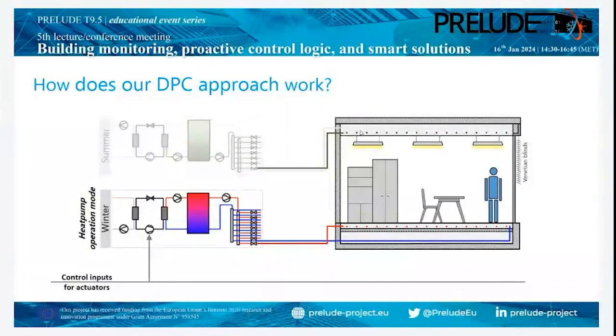We consider a time step size of 15 minutes, so from the optimization algorithm we get 96 values for switching our heat pump on or off for the next 24 hours - every 15 minutes we get a value.